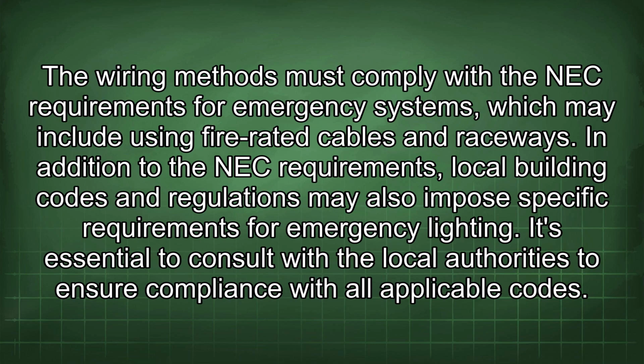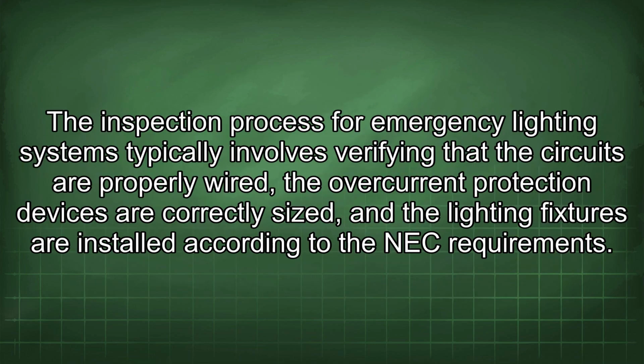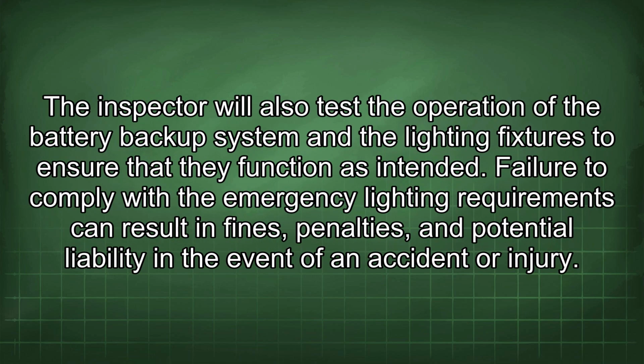and raceways. In addition to the NEC requirements, local building codes and regulations may also impose specific requirements for emergency lighting. It's essential to consult with the local authorities to ensure compliance with all applicable codes. The inspection process for emergency lighting systems typically involves verifying that the circuits are properly wired, the overcurrent protection devices are correctly sized, and the lighting fixtures are installed according to the NEC requirements. The inspector will also test the operation of the battery backup system and the lighting fixtures to ensure that they function as intended.